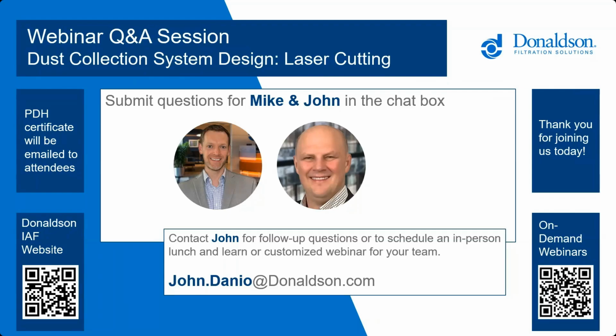So if they're seeing some excessive loading on the filters, something's going on that needs to be addressed, right? Something's not quite right in the design, or we need to pre-coat the filters or do something different in the design.